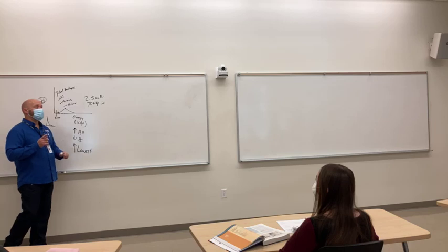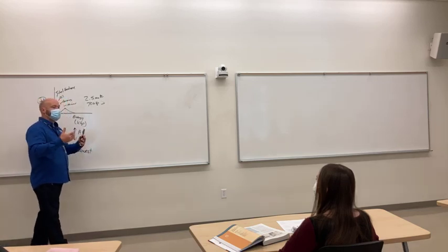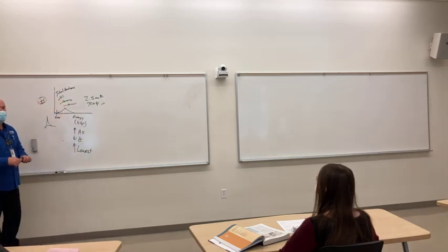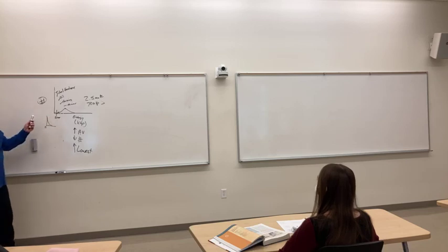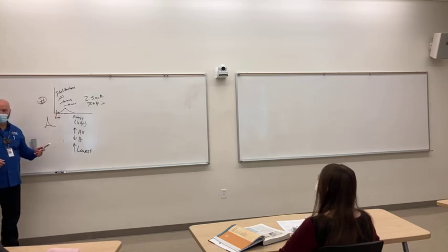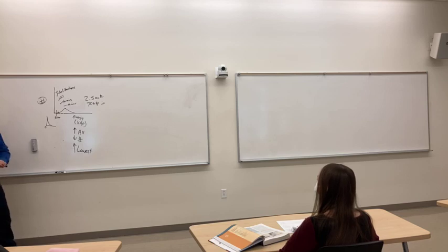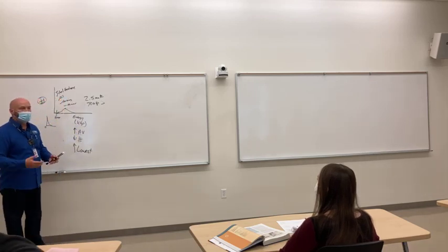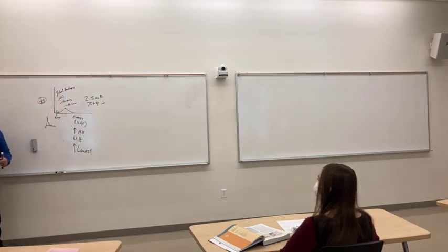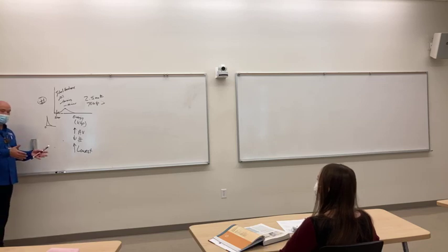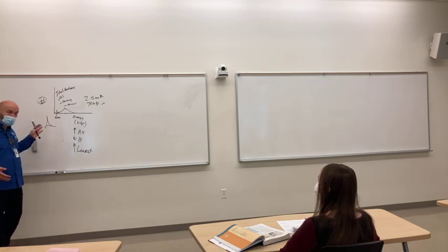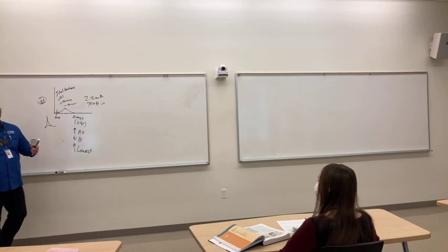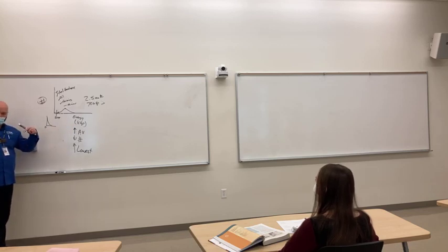Is that going to come with implications for image receptor exposure? Yes. Absolutely, right. So even though these are low energy X-ray photons, might there be a possibility that they would have the energy to reach the image receptor? Answer is yes. So if they possibly could reach the image receptor, they change the image receptor exposure, and by virtue of removing those, your image receptor exposure is going to go down with increased filtration.